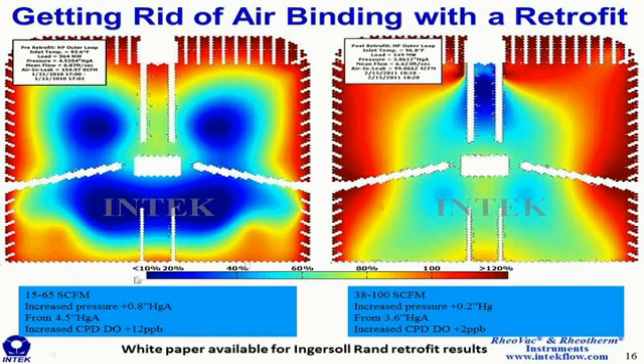Pre-retrofit, over on the left-hand side, you can see in the blue box below that a test conducted where we increased the air in leakage from 15 to 65 SCFM resulted in a condenser pressure increase of 0.8 inches. Not only that, but the condensate chemistry measurements on the condensate pump discharge showed a 12 ppb increase in dissolved oxygen. So all of the condensate falling through this bundle, going through those airbound regions, is picking up the air gases, the oxygen is dissolving into the condensate and it shows up in the condensate chemistry measurements.